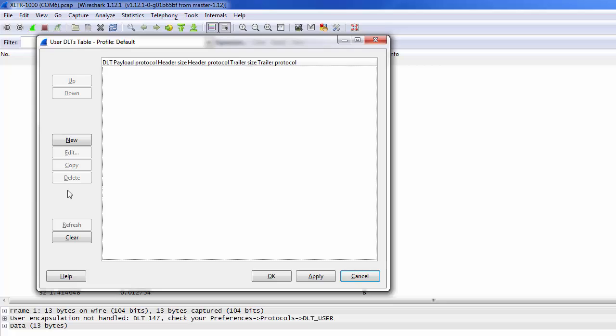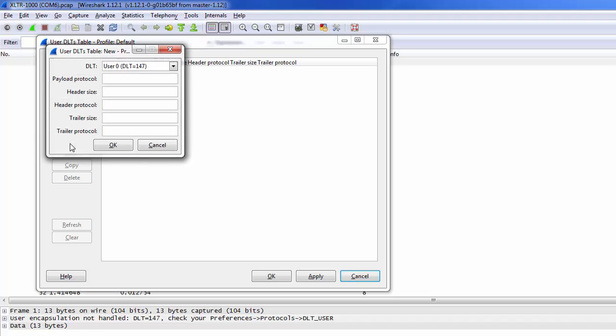This opens the User DLTs table. Click the New button to add a new entry. Make sure User 0 is selected for the DLT, and enter MBRTU into the Payload Protocol field to tell Wireshark to use Modbus RTU to decode the packets.